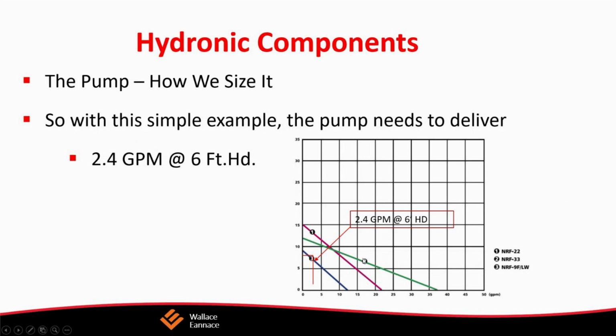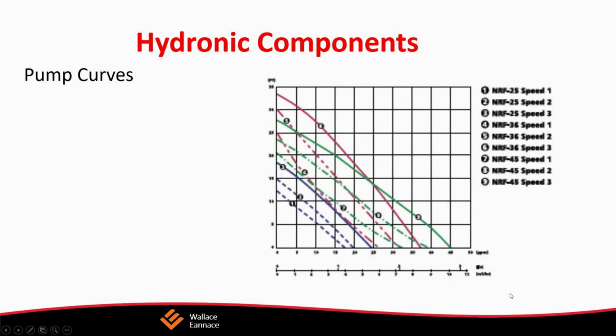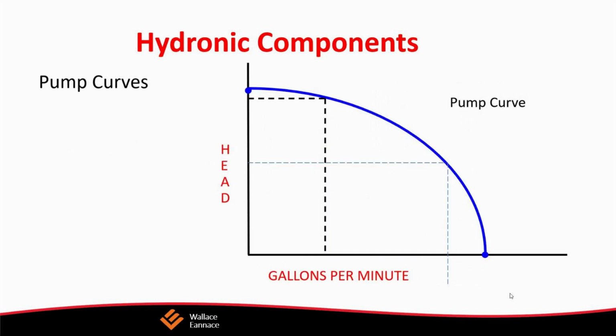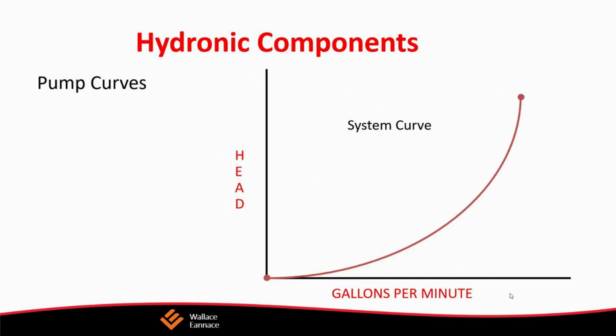So let's go back to how we size it and do a simple example. If we have a zone with 50 feet of 3/4 inch baseboard rated at 160 degrees F, we would need 50 additional feet of piping. So 50 times 480 BTUs is 24,000 BTUs. Divide that by 10,000, and 24,000 BTUs divided by 10,000 gives us 2.4 GPM. So we have 50 feet of baseboard and also 50 feet of additional piping to get to and from the baseboard.